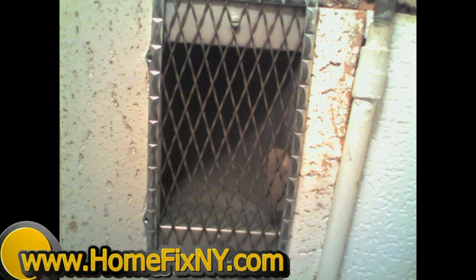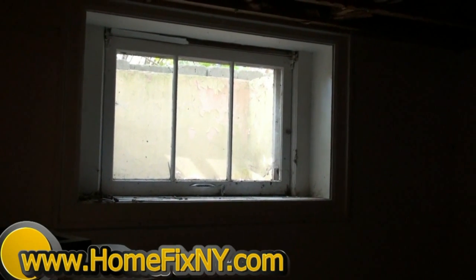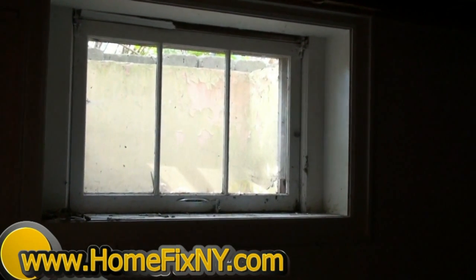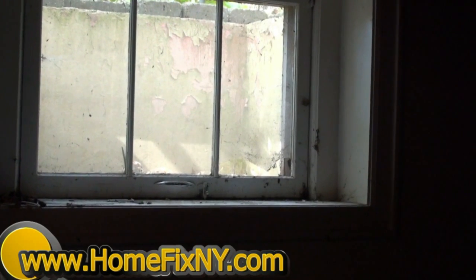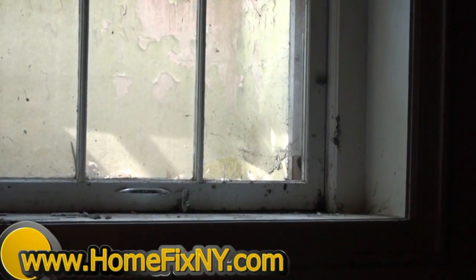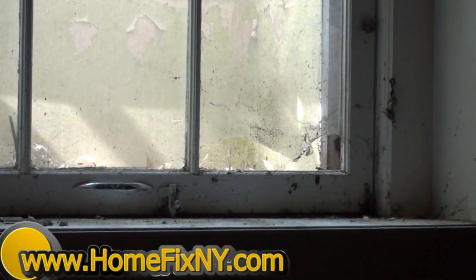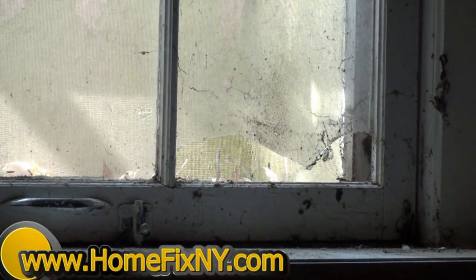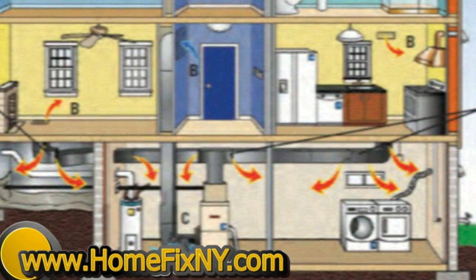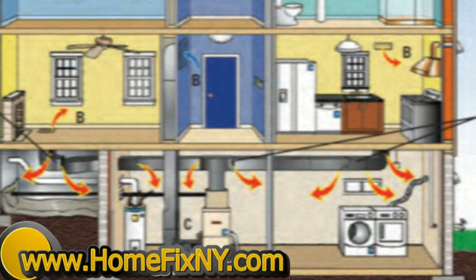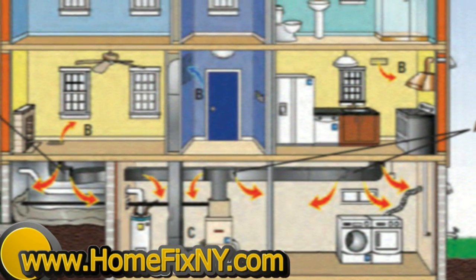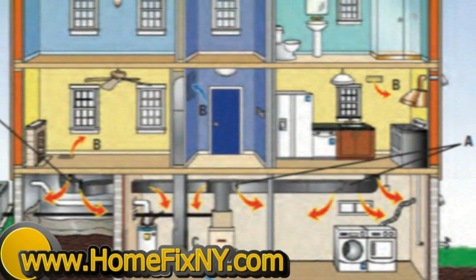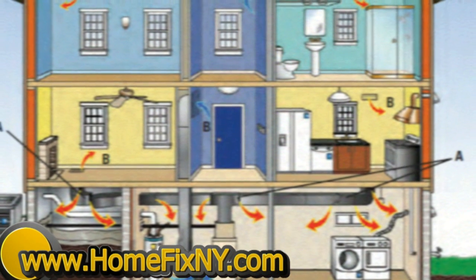This is one of the open registers that they had in the basement. There was another one just like this, so they had basically 4 wide open registers in a pretty small basement. And all that heat was leaking out through the basement through single pane glass windows that had never been replaced. The upstairs had been totally renovated, but the downstairs windows were just single pane and they were cracked and broken. So you can imagine what this was doing to their energy bills. The warmest room in your house has the worst windows, and they're cracked and they're leaking. All that energy and that expense of heating that air or cooling that air is just going right out the window.